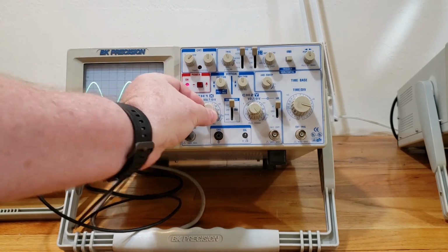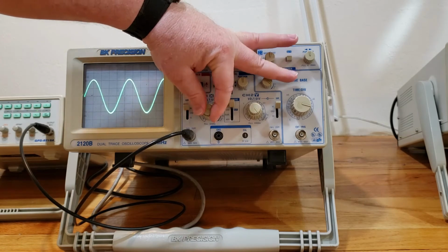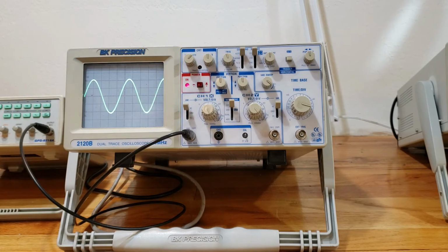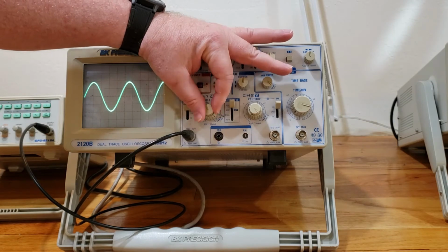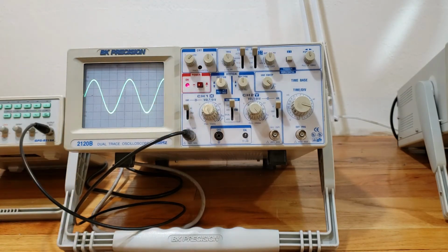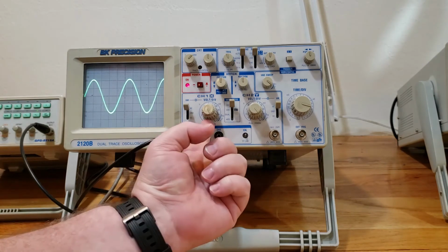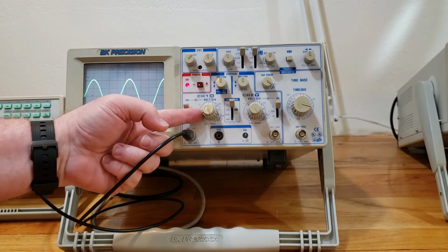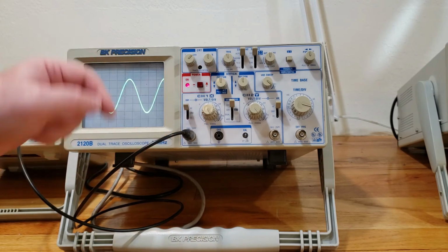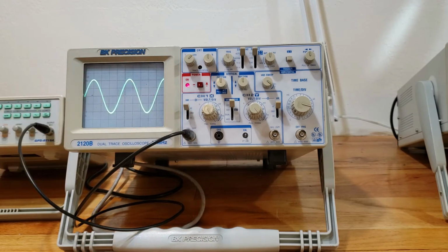Now, this knob also has a feature where I can make an adjustment so that I can calibrate. If I know that I have a specific voltage on output and this isn't quite matching that, I can calibrate the scope to meet that voltage. Now, the actual volt division part of the knob is this part right here, the larger part of the knob, the side of the knob. You'll notice the indicator right here on the side. Right now it's pointing to 2 volts. We'll talk more about what the divisions mean, what that 2 volts means, a little bit later.